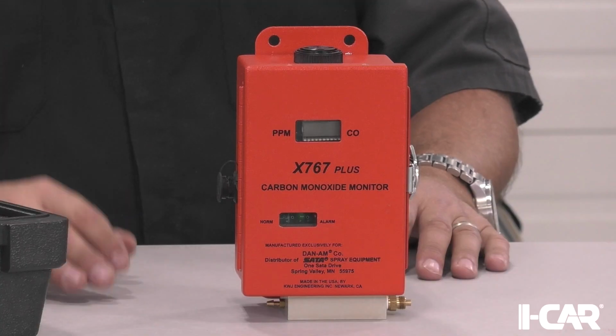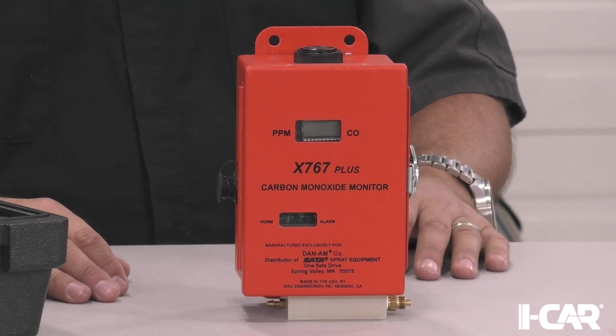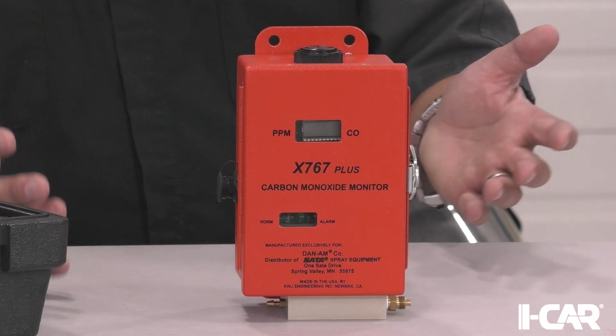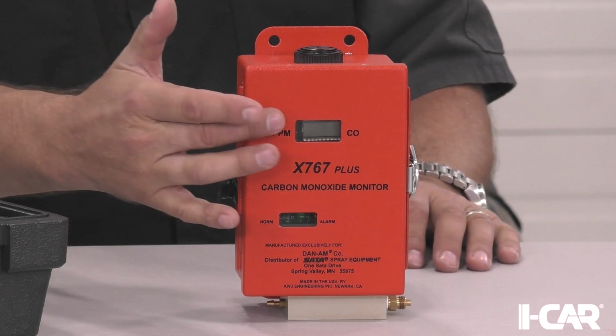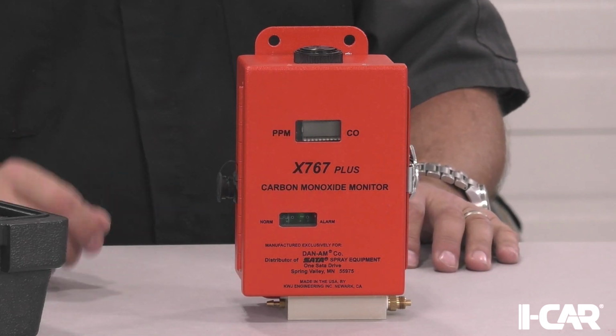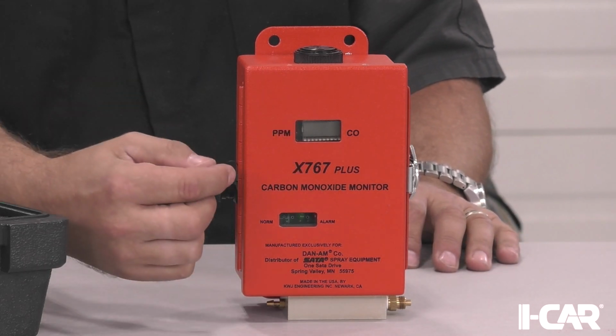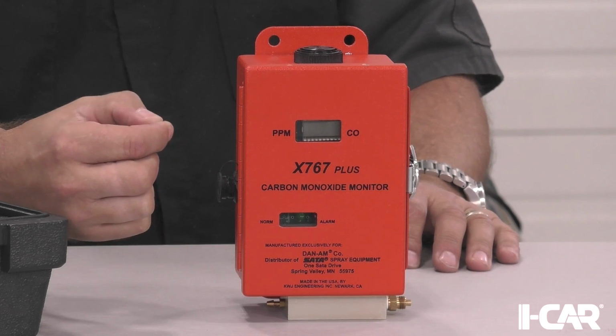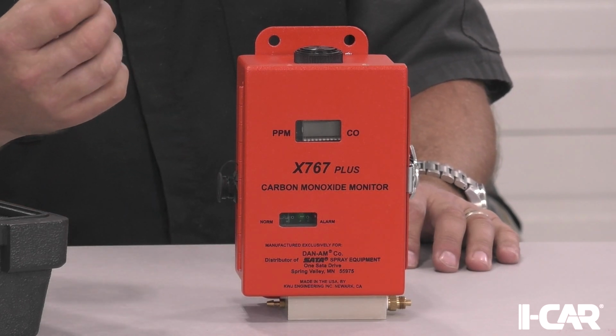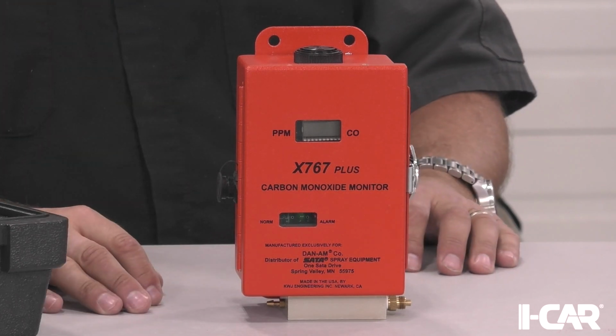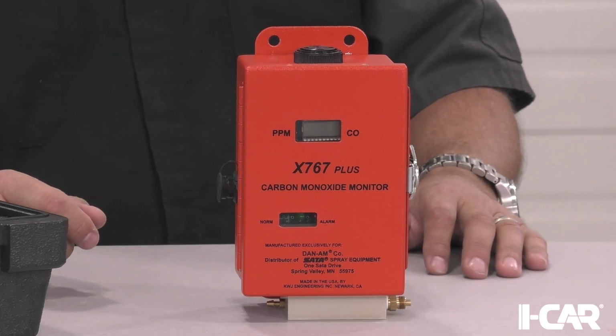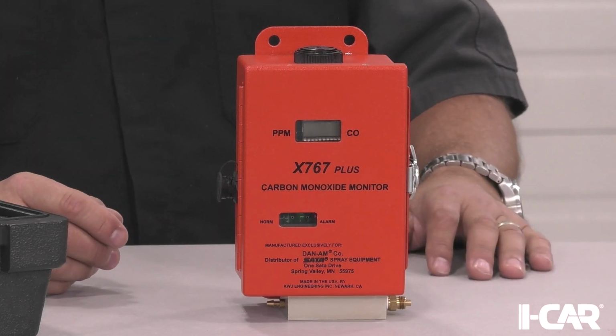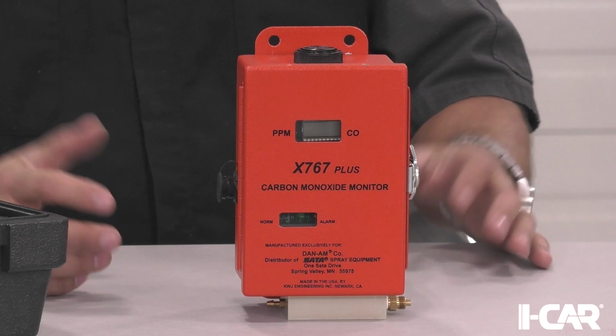One of the requirements to prove grade D air is below 10 parts of carbon monoxide. This monitor has all the features it needs. It has an LED screen that tells you how many parts per million you have, a blinking green light so you know it's on, a little red flashing light that lets you know it's sensing, and a very loud audible alarm, which we set off this morning to show that.